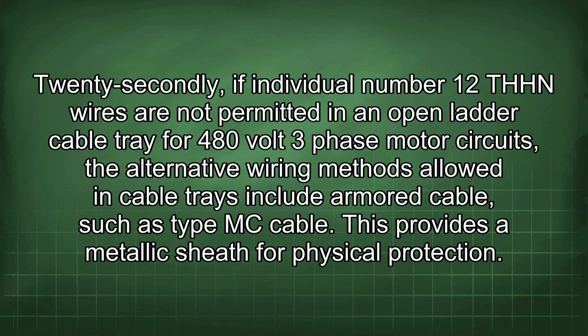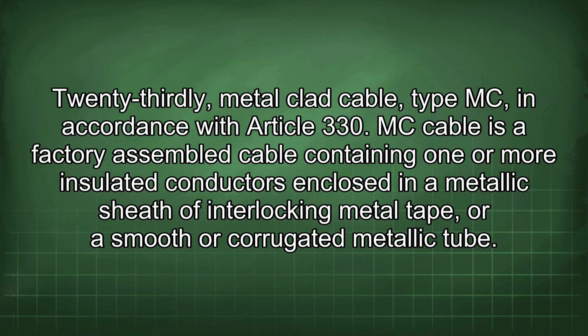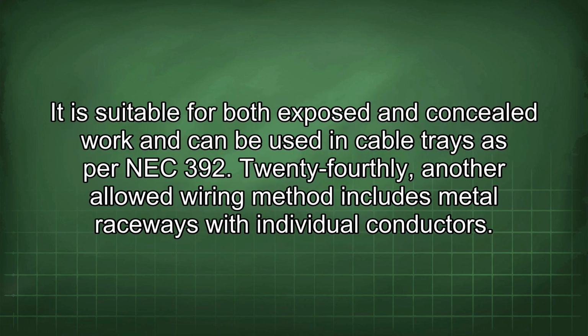22ndly, if individual number 12 THHN wires are not permitted in an open ladder cable tray for 480 volt three-phase motor circuits, the alternative wiring methods allowed in cable trays include armored cable, such as Type MC cable. This provides a metallic sheath for physical protection. 23rdly, metal-clad cable, Type MC, in accordance with Article 330. MC cable is a factory-assembled cable containing one or more insulated conductors enclosed in a metallic sheath of interlocking metal tape or smooth or corrugated metallic tube. It is suitable for both exposed and concealed work and can be used in cable trays as per NEC 392.